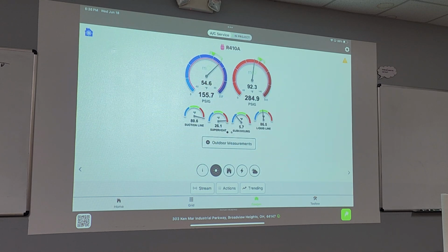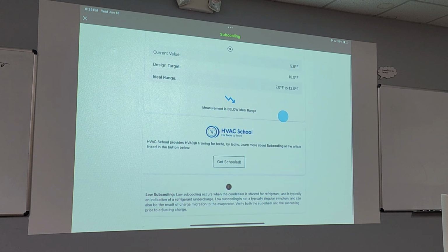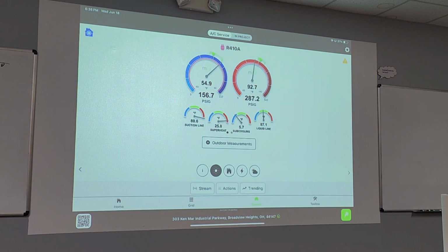Same thing with "system may be undercharged with refrigerant." I've seen it where my subcooling is just a tenth of a degree in or out of tolerance. And again, if you have a question on what the measurement is supposed to be, click on the gauge. It'll bring up current value, target, and tolerance. So if my current value was 6.9 and it's teetering on the fence of 7.0, you'll see the score jump up and down as it goes in and out of range.